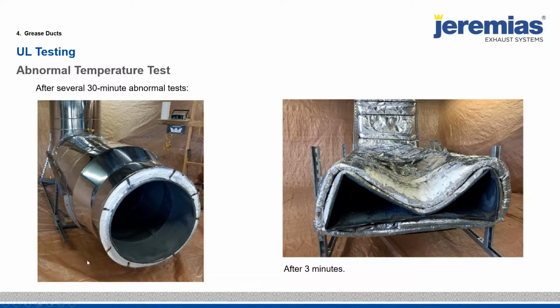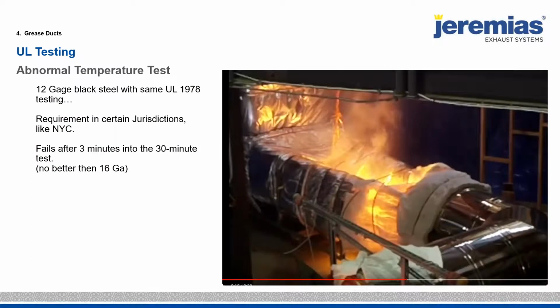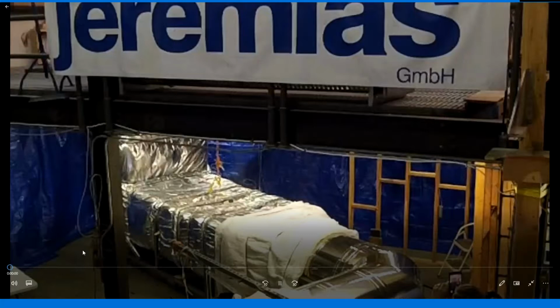Look at the right-hand side. That's the carbon steel system after 3 minutes. Now, we do a lot of work in New York City, so we know that the 12 gauge black steel is the standard there for a field welded system, 12 gauge. So what we did, and we're working a lot with the authority there, we actually brought these folks into our lab and we tested a 12 gauge black steel system.